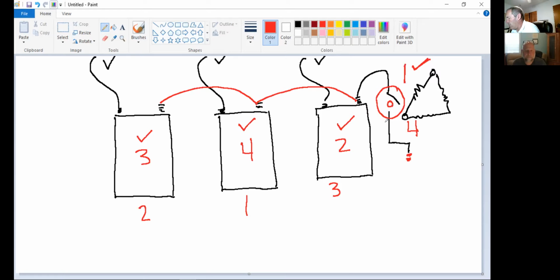How many people have I confused? You just went in reverse, correct? Right, and that's really when I did the energize and de-energize without the grounding switch, I did the same thing - 1, 2, 3 for re-energize and 3, 2, 1 for de-energize without the grounding switch. I'm adding the 4th location here to prevent ferroresonance and voltage spikes.